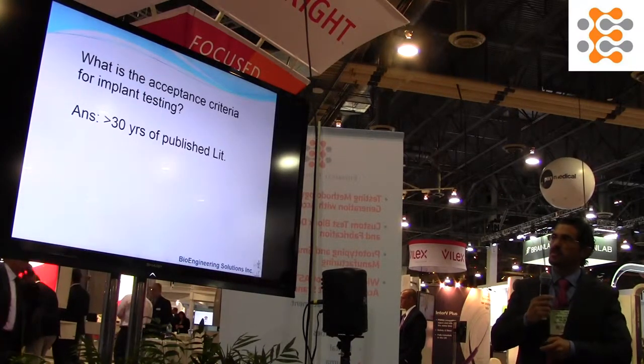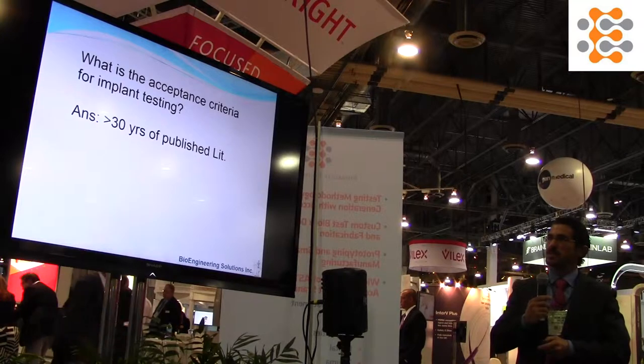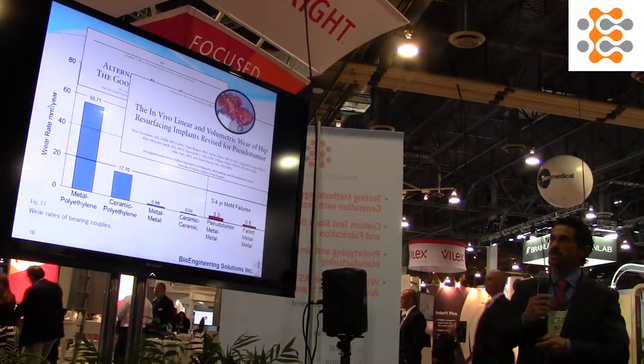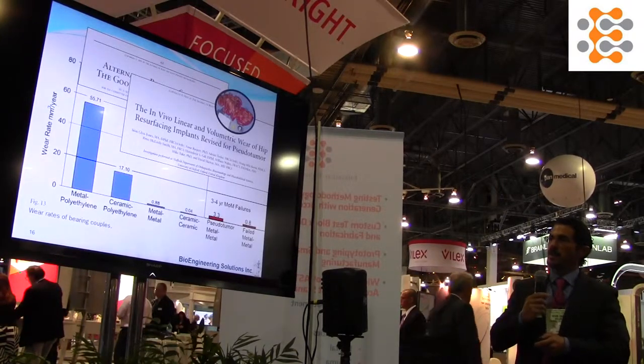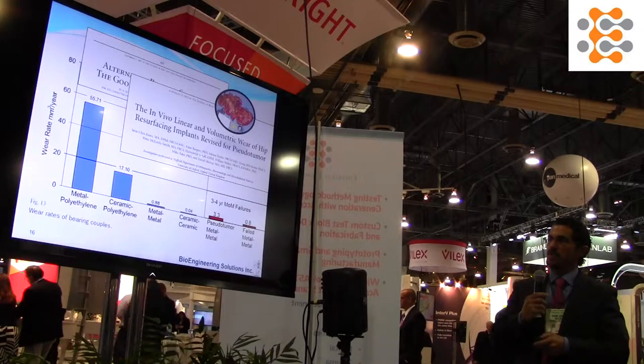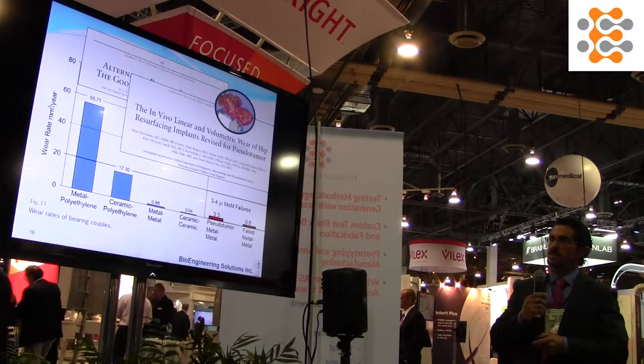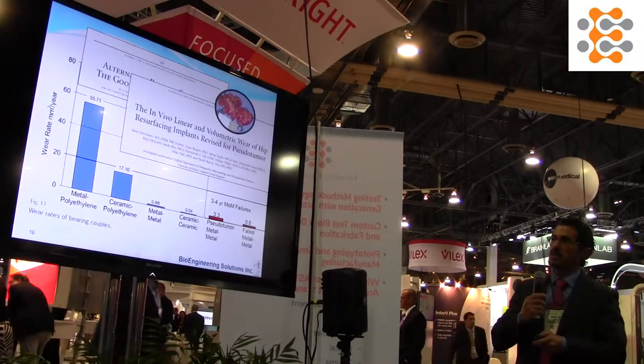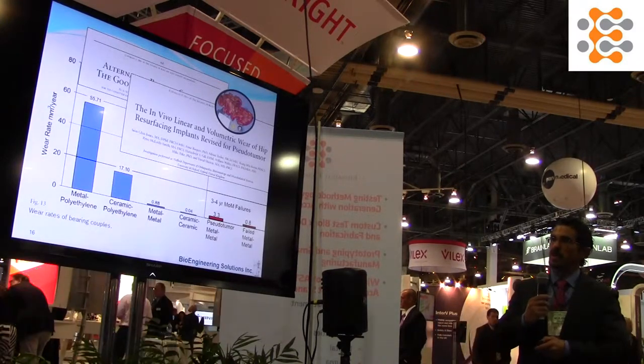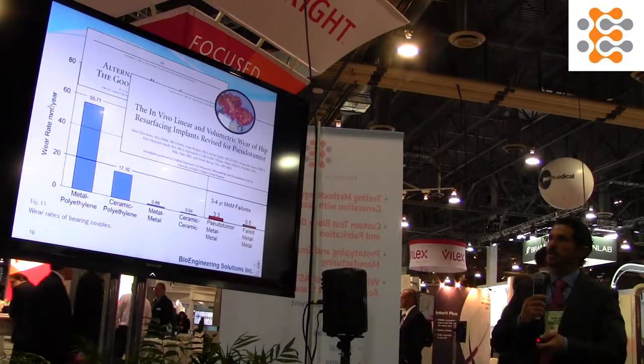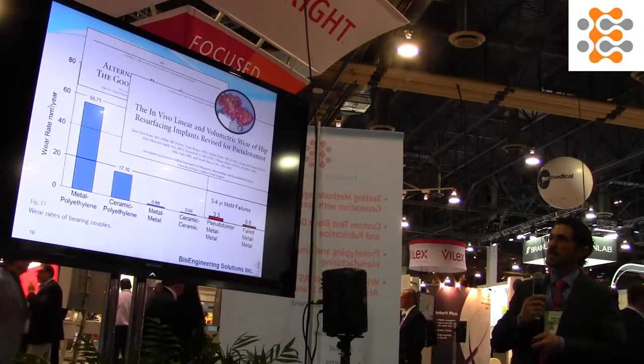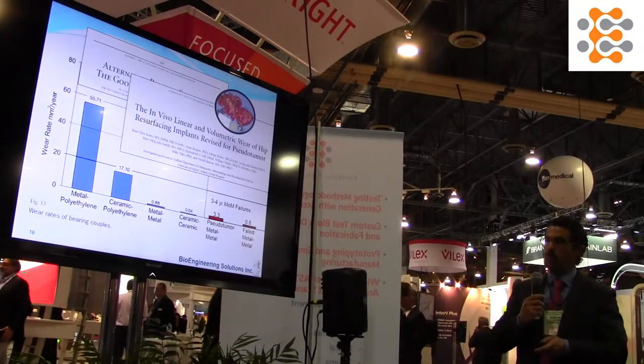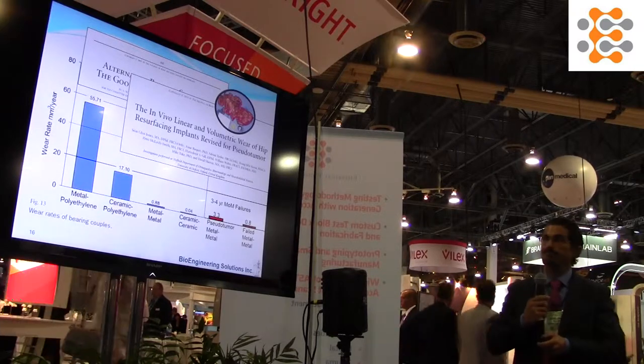What is the acceptance criteria for implant testing? The answer is 30 years of published literature. But this is not the end-all be-all. Here we see the wear rates from metal-on-poly all the way down to failed metal-on-metal, and the wear rates were pretty low for those failed metal-on-metals.